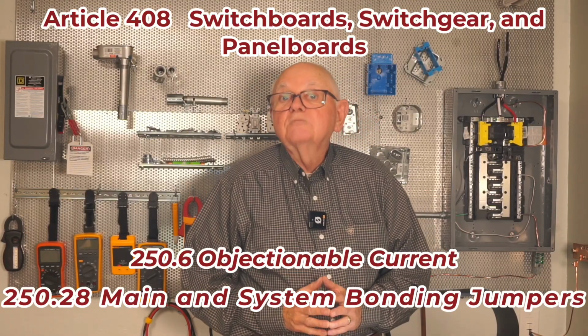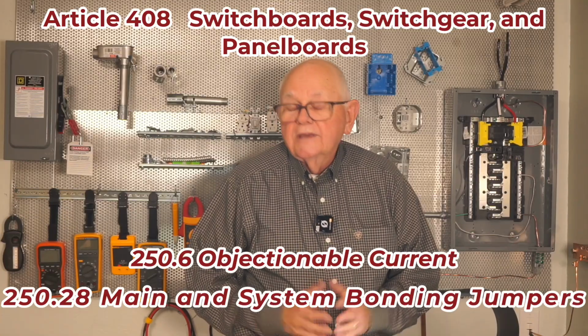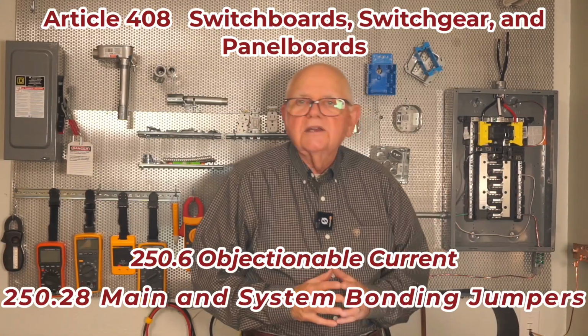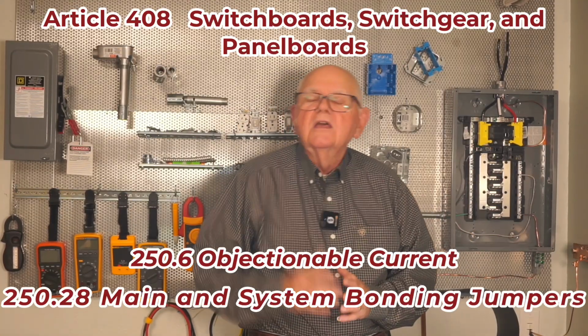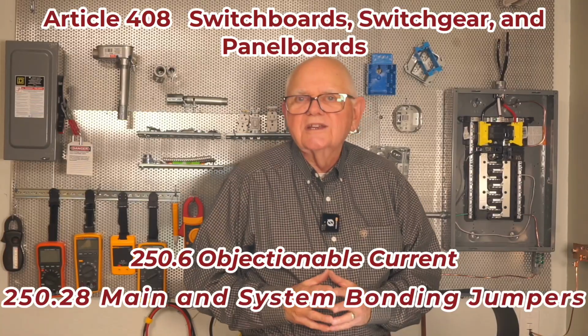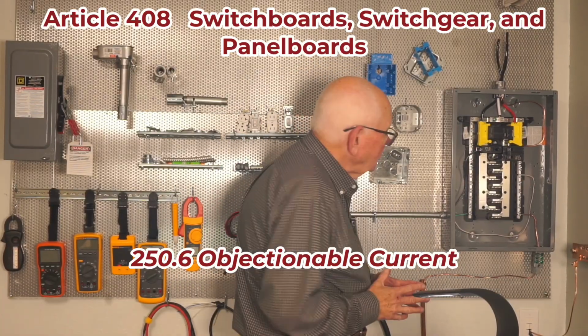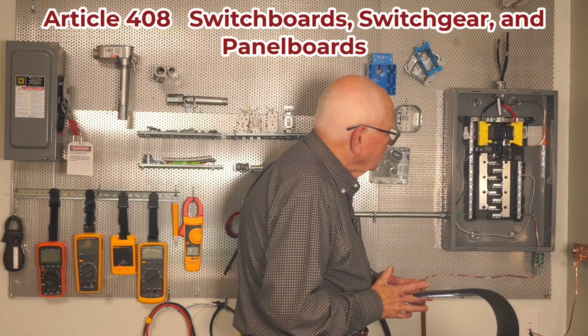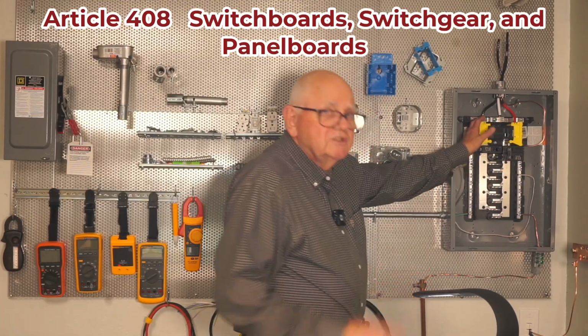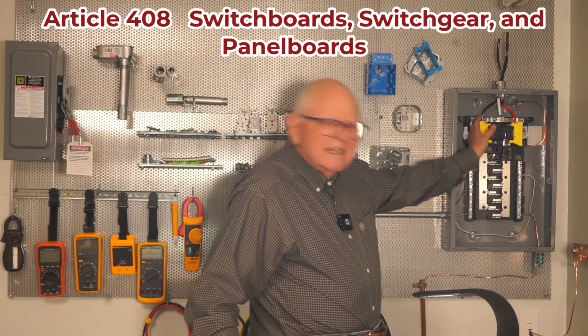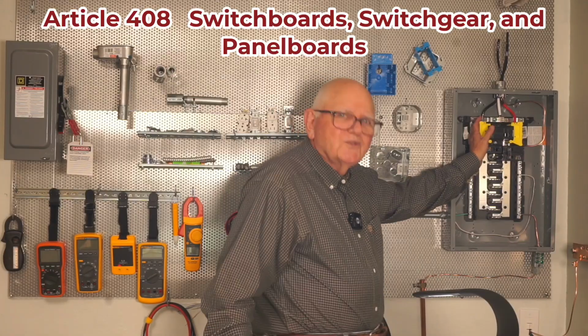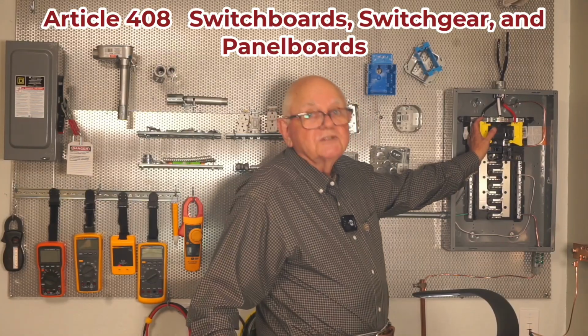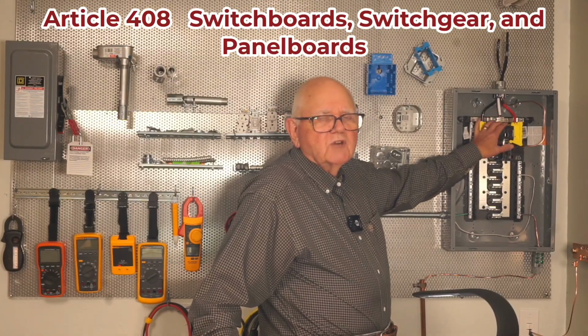250.6 talks about objectionable current. So what do I have to do? I have to remove that bonding jumper in my sub panel. So pay attention to those requirements. That can get you into a lot of trouble really quick. 250.6 then. Also something else, Article 230: these yellow things up here have to be there. It doesn't say these yellow things. 230.62, Article 230 is on services, and it says on service equipment.